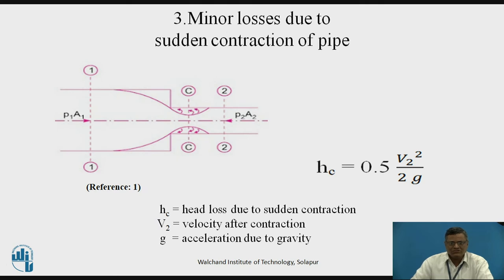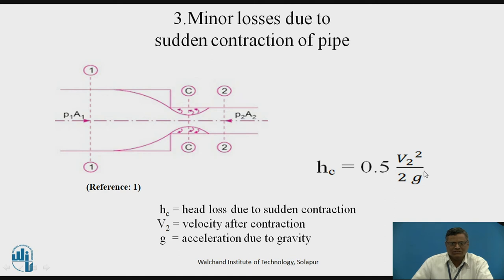The third type is minor loss due to sudden contraction of pipe — exactly opposite to the previous case. Here the cross-sectional area has suddenly decreased at a particular section. Due to the sharp edge, losses occur, and at section CC, the vena contracta is formed where the cross-sectional area of the flow jet is smallest. The flow then expands to fill the full pipe cross-section at section 2-2. The head loss due to sudden contraction equals 0.5 × V2² / 2g, dependent on the velocity at section 2 only.